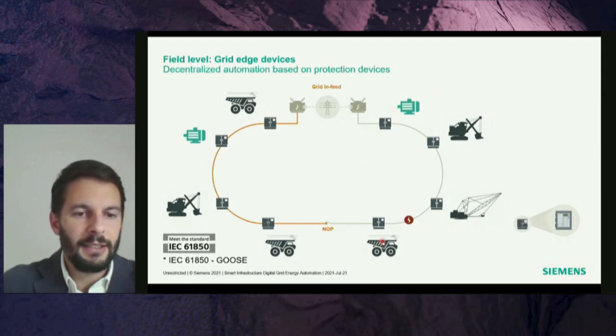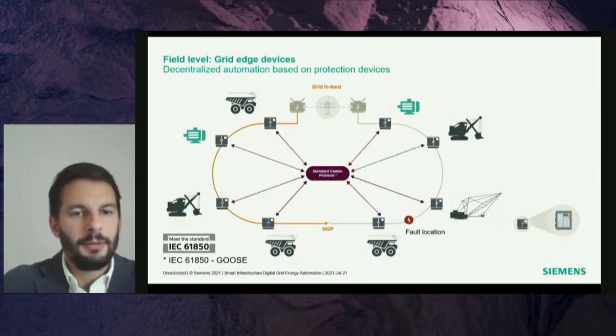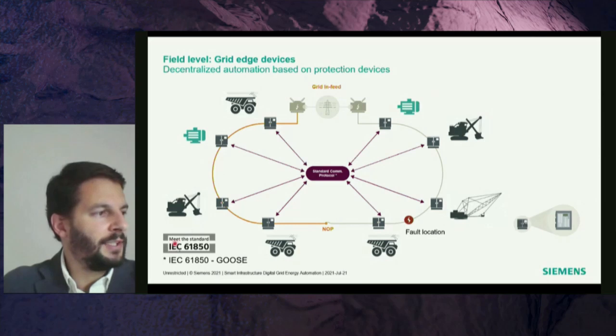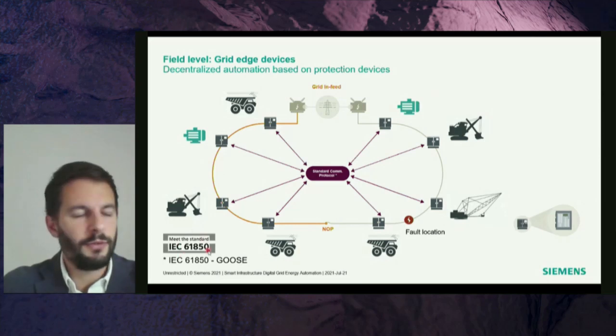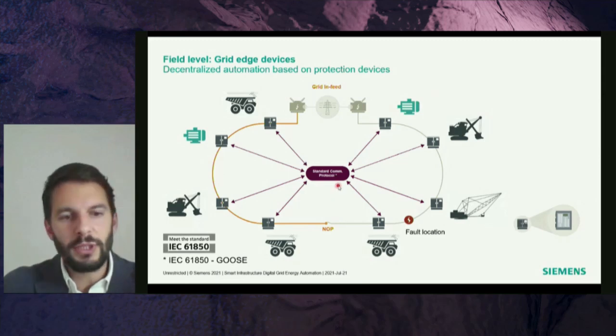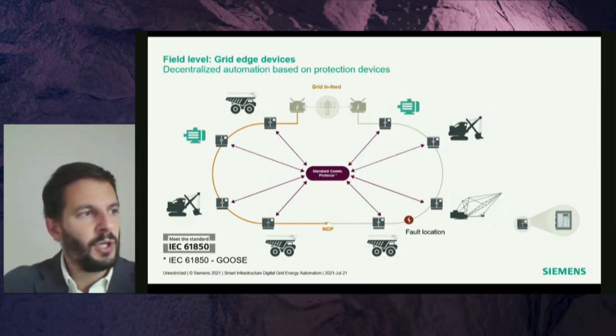So how the system operates, again, based on this IEC 61850, as you can see here on the bottom of the screen: all these grid devices installed on these different stations are basically interfacing between each other, multicasting so-called GOOSE messages, and informing about the grid status. Once this information is available at the different nodes, we are in a position to properly isolate the faulted section, as you can see here.